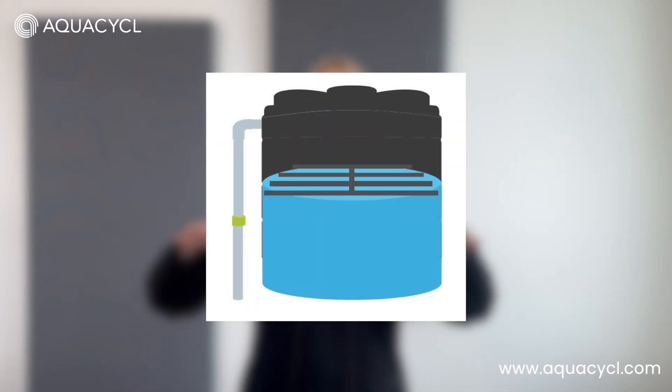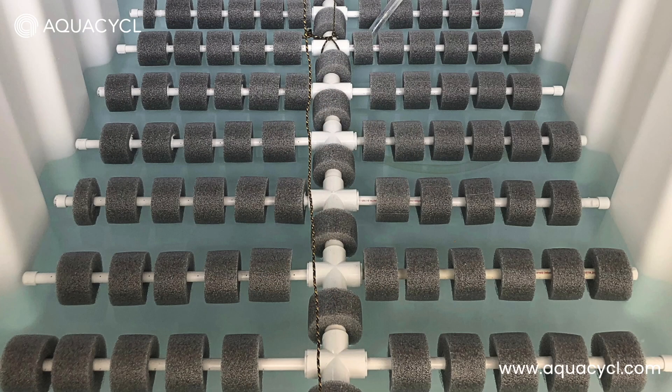Digitization is actually a big part of the success of this product. What we're doing is we have a floating manifold that retrofits into any tank — it sits and floats on the volume of the bulk water inside the tank, rising and falling depending on your production. What's really important is what that manifold is doing: blowing air just across the surface of the water, encouraging the growth of sulfide oxidizers — bacteria that take that sulfide gas and oxidize it into elemental granules bound in biomass.